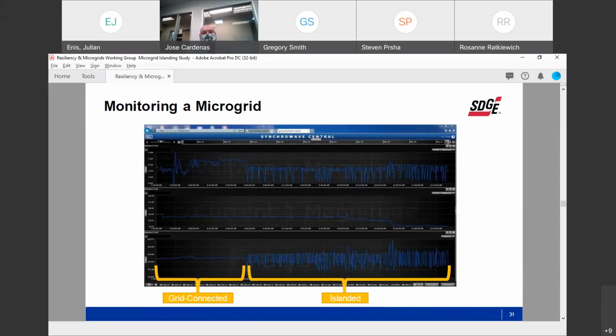Another useful use for this Synchrowave data, this PMU data, is that whenever we are unsuccessful, this also brings in breaker status, what the system tripped on, the 51, all your protection elements. We can develop a timeline to see what was the trigger that caused us to lose the microgrid. Everything is GPS timestamped, so we can take a deep dive into this, do an analysis, determine what the issue was, and help us develop our operating procedures to be successful.